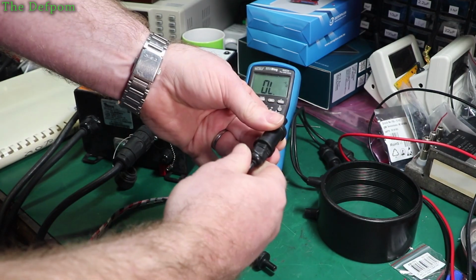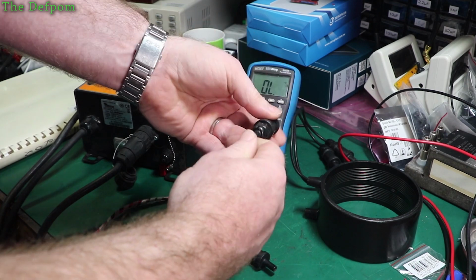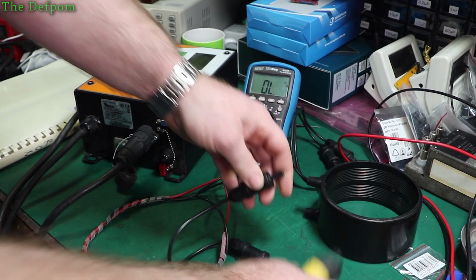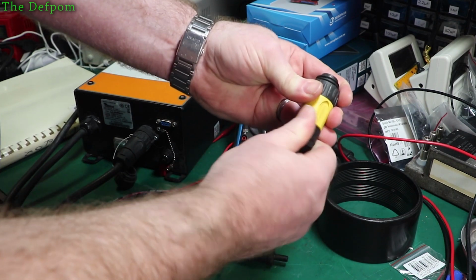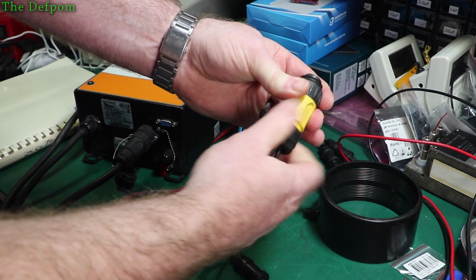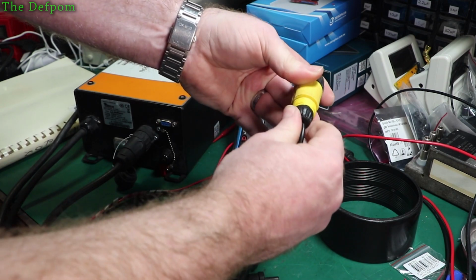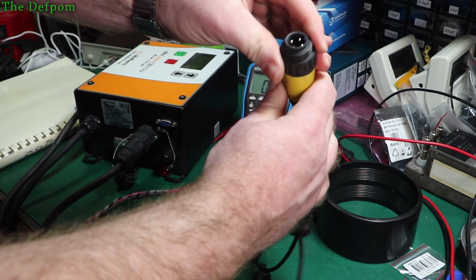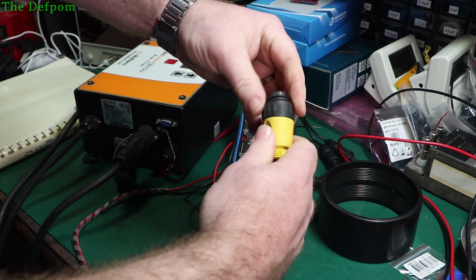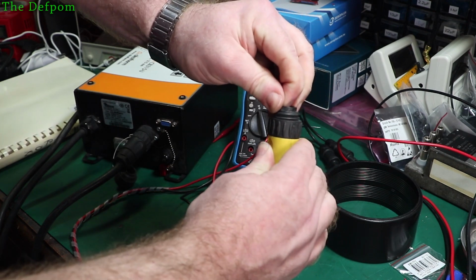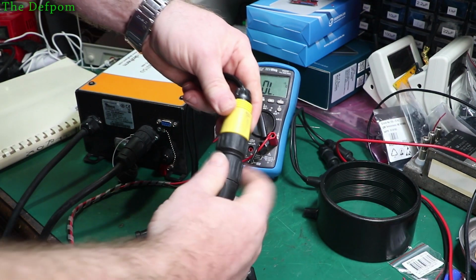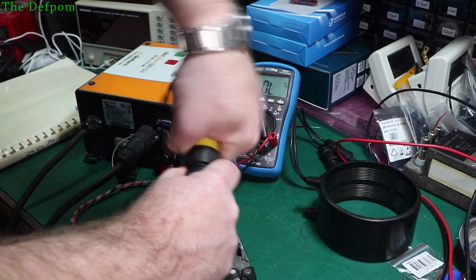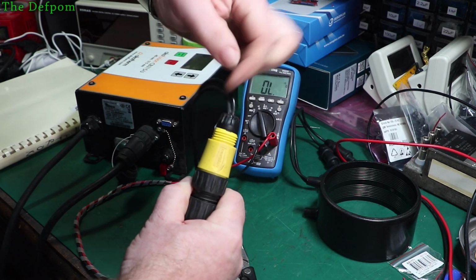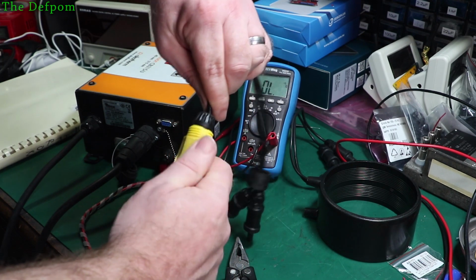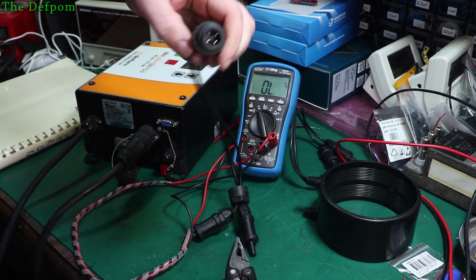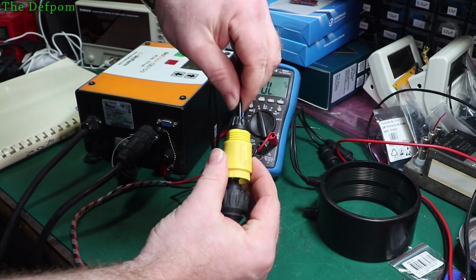So let's pull apart. How am I going to pull these apart? I'll pull this one apart. And then we'll see if this end looks like it's been pulled off, because it's going to be one end or the other. This is a gland. Now this will unscrew off here, but these can be a bit of a pain, because you've got to unscrew from this piece here. I'm used to these connectors, I've seen them before. Okay, I'll just plug it into the other one so I can use that to hold it and unscrew from there. You see I'm actually trying to avoid spinning that in the gland too much. It should go with it. There we go, that's now off. Let's pull the plug out. Should be able to push it out.